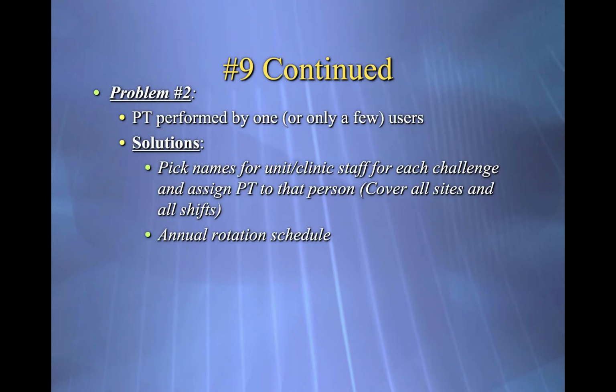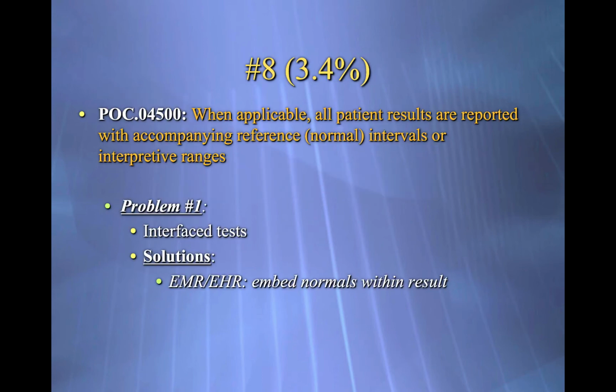The PT is always performed by one or only a few of the users, not all the users. So again, having the point-of-care team go out and assign different individuals on different shifts, keeping track of who did it, so you cover all sites and all shifts, or have some kind of annual rotation schedule, can get you through that one. Number 8.